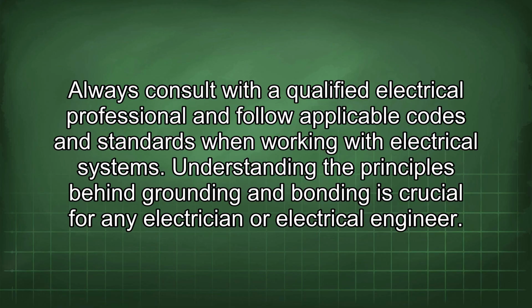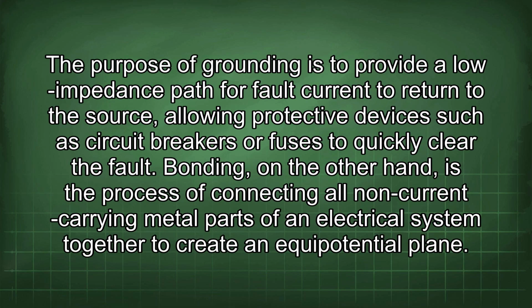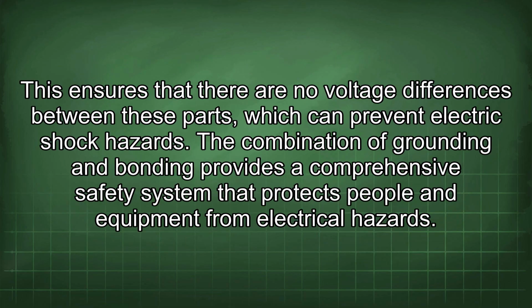Understanding the principles behind grounding and bonding is crucial for any electrician or electrical engineer. The purpose of grounding is to provide a low impedance path for fault current to return to the source, allowing protective devices such as circuit breakers or fuses to quickly clear the fault. Bonding, on the other hand, is the process of connecting all non-current carrying metal parts of an electrical system together to create an equipotential plane. This ensures that there are no voltage differences between these parts, which can prevent electric shock hazards. The combination of grounding and bonding provides a comprehensive safety system that protects people and equipment from electrical hazards.